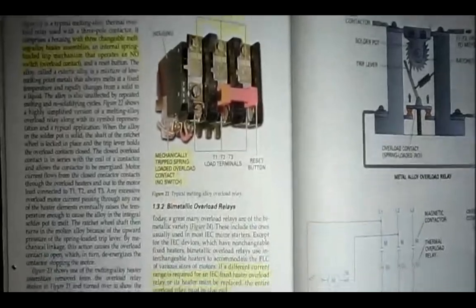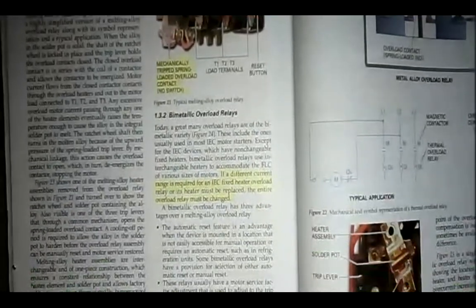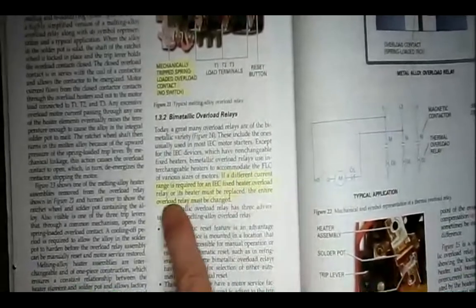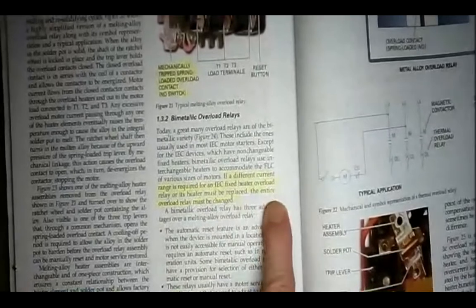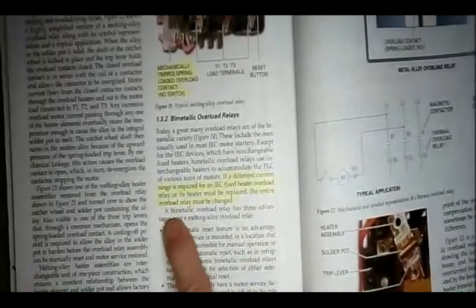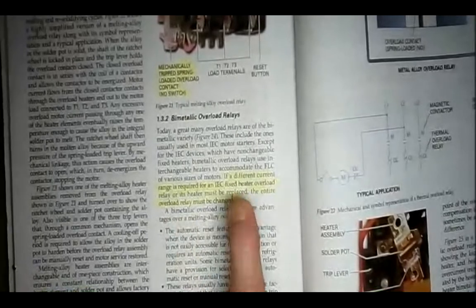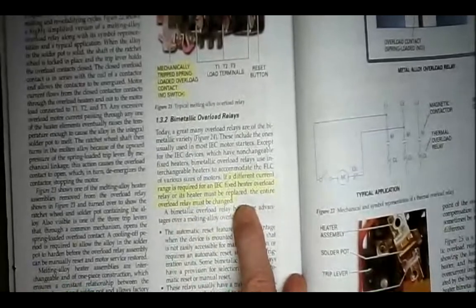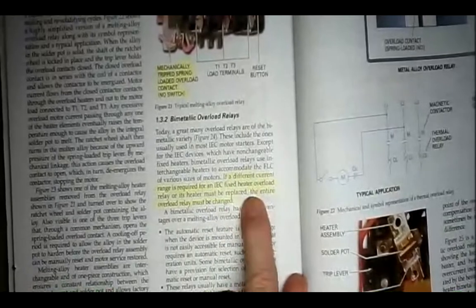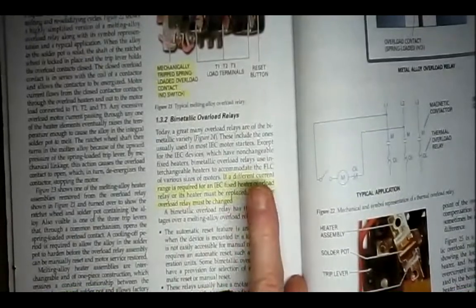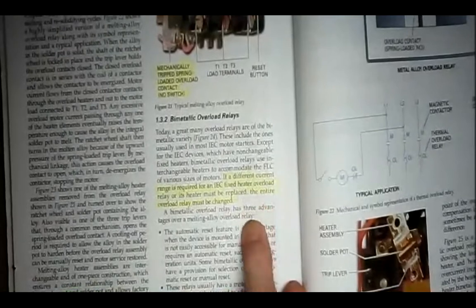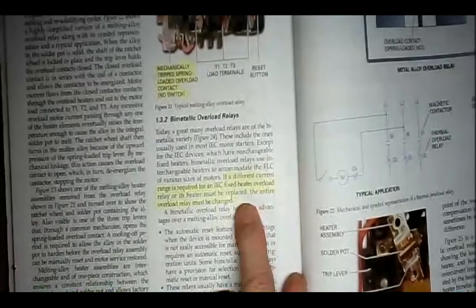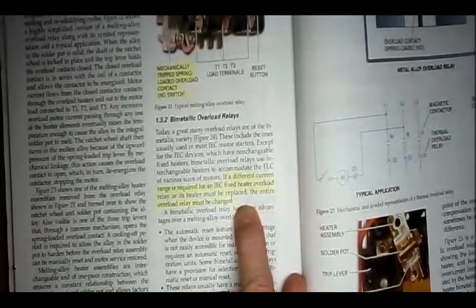I have one more highlight, and then I'm going to look at a picture and explain all of this to you. But the other highlight on page 18 on the right-hand side says, if a different current range is required for an IEC fixed heater overload relay, or its heater must be replaced, the entire overload relay must be changed. The NEMA, the ones we use here, Square D, GE, the heaters are replaceable. You can take the heaters out and put in new heaters. The IEC, International Electrotechnical Commission, those are not replaceable. It's all one sealed unit. If the overloads go bad, if you need a different size overload, you need to change out the entire overload block.